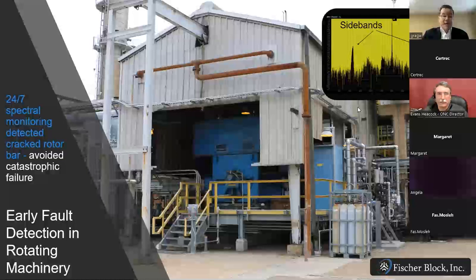But in this case, there was an overheating rotor bar, which eventually cracked. And that overheating rotor bar is typically from a problem with the rotor windings or even stator windings. But that distortion will show up in the electrical signal when we're doing a continuous FFT frequency extraction on all the signatures that we capture. And you can see there the sidebands indicating a developing problem. And then they will schedule that. And we watch those sidebands grow over many weeks and months. So they can plan their maintenance without having to be reactive and be much more proactive and resolve issues before catastrophic failure.